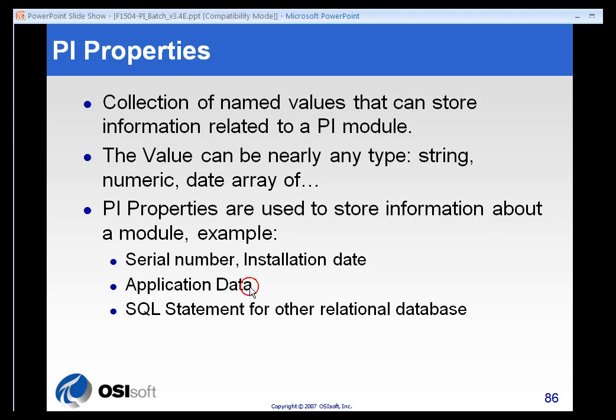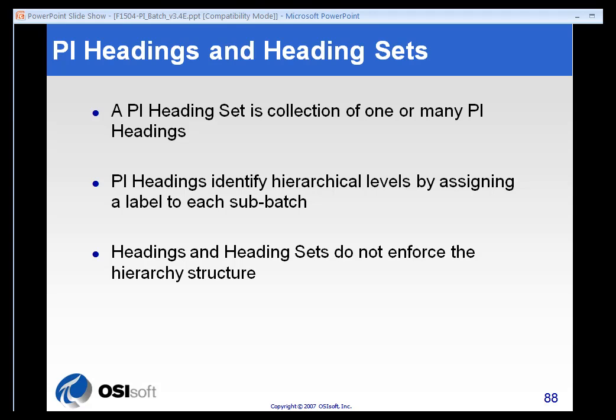Some people use properties to store application data with custom applications, or they use them to hold SQL statements in order to connect to other databases. There are a lot of uses for PI properties. Just remember that there are aliases and properties — aliases are tag values, and properties are constants. The Module Database also has the ability to store what's called heading sets. A heading set is a collection of simple identifiers that we use in order to be able to search. They do not enforce any sort of hierarchy structure — they are simply labels that are helpful in terms of searching.